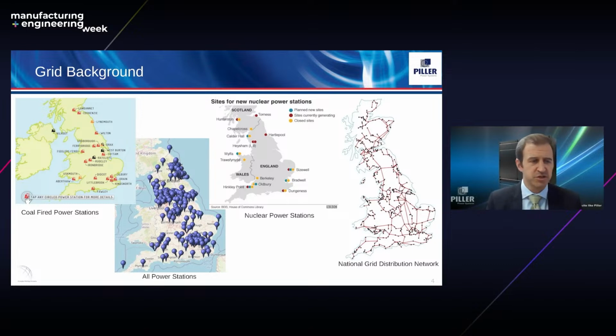Looking at the distribution of power generation across the country, there are certain concentrations, which led to the layout of the supergrid at 275 and 400 kV. This network was built focused on these concentrations of power generation, which were mostly high-power synchronous machines offering high inertia levels with high fault current contribution, resulting in a stable network and predictable performance during fault scenarios. However, these legacy power stations no longer offer the best forms of generation to support the grid of the future.